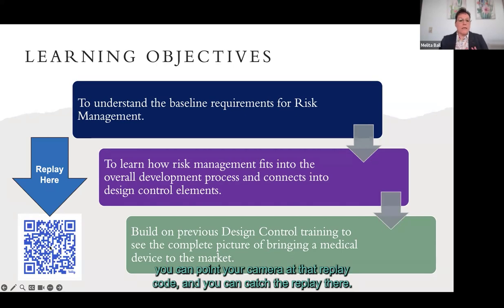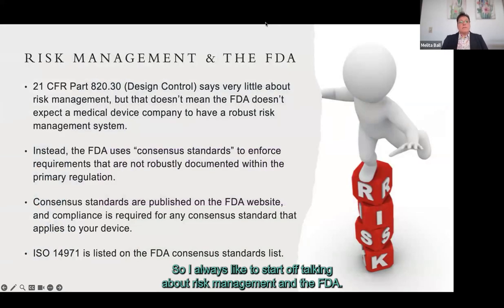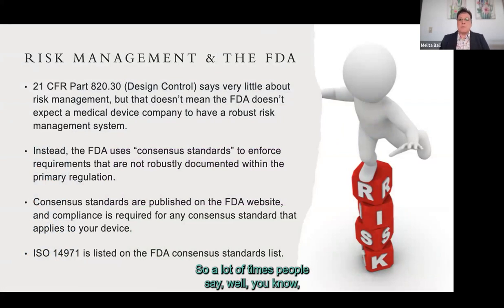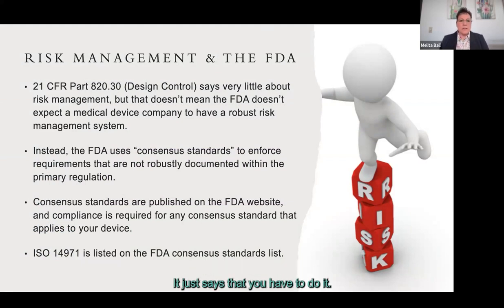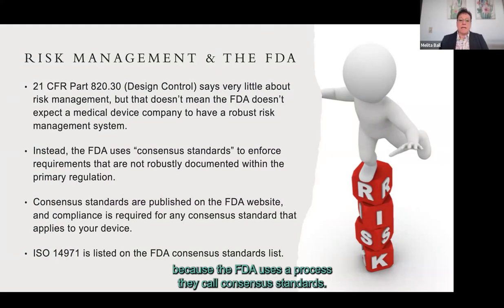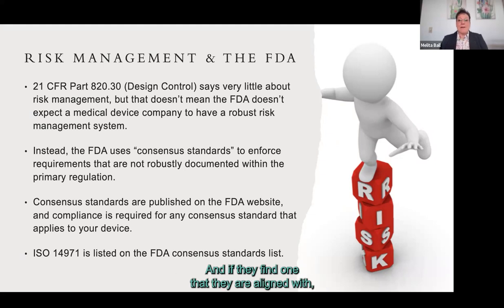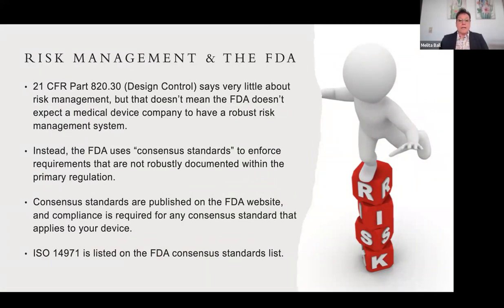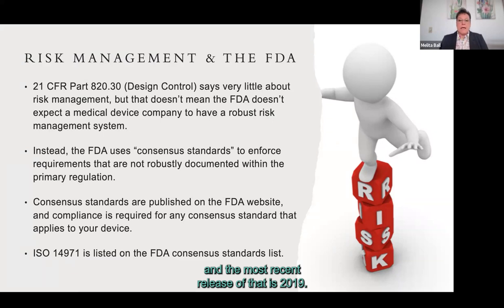I always like to start by talking about risk management and the FDA. A lot of people say they've read 21 CFR Part 820.30 for design controls and it doesn't say a whole lot about risk management — it just says you have to do it. There's a very specific reason for that. The FDA uses a process called consensus standards: they scour the world for the best standards, and if they find one they're aligned with, they add it to a consensus standards list and simply point people to that standard.